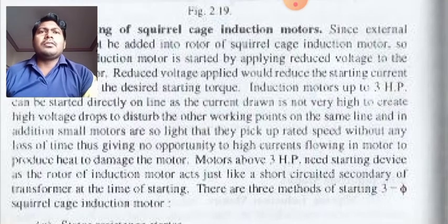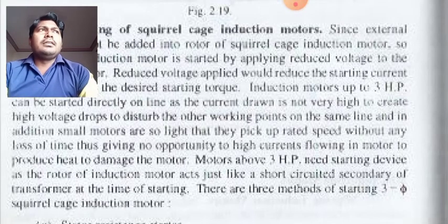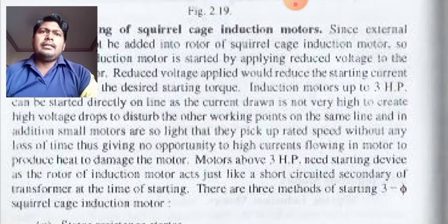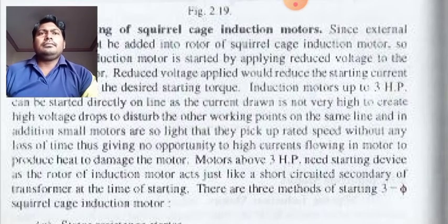At the same time, I am also saying that if the motor's rating is below 3 HP, there is no need for a starter or to limit its current, because below 3 HP the amount of current drawn is acceptable and not dangerous for the motor. As a result, we can go for direct online starting, and if it is higher than 3 HP, we have to go for starters. So there are different forms of starters.